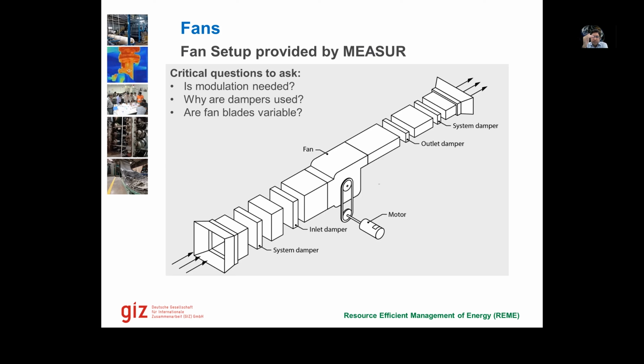If the demand varies constantly over a number of days, for example, these kinds of blades are usually used in weaving and spinning ventilation systems, where we have variable speed, variable angle blades. So we change the angle to change the flow rate. But the best way is to use a variable frequency drive, measure the requirement on the demand side, and modulate the VFD and motor accordingly.